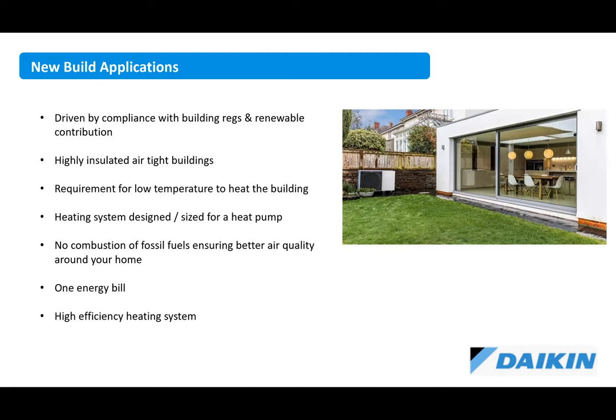You only need low temperature to provide the heat in this building. So that is a very happy marriage between a heat pump and the new type of buildings that we've been building in Ireland since 2019. The heating systems are designed and sized for heat pumps.